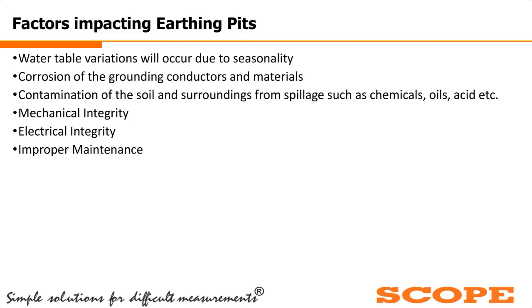Then the next is, if the grounding conductors, the plate rods or the pipes, this type of earthing conductors get corroded, then the effective earthing resistance will be hampered, and the earthing pit performance will be hampered by this type of corrosion. Then the next is contamination in soil. This type of problem generally occurs in chemical or oil industries, where components such as chemicals, oils, or different types of acid contaminate the soil or the surroundings of the conductor. This will also impact the earth pit performance.